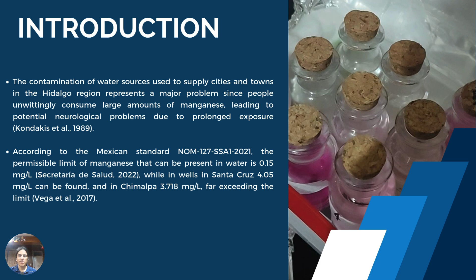Shockingly, wells in Santa Cruz and Chimalpa, regions of Hidalgo, contain up to 4.05 milligrams per liter and 3.718 milligrams per liter respectively. This is far exceeding the Mexico safety limit of 0.15 milligrams per liter dictated by the norm 127 SSA1 2021. Our portable device detects manganese by measuring permanganate absorption at 525 nanometers using the Beer-Lambert principle.